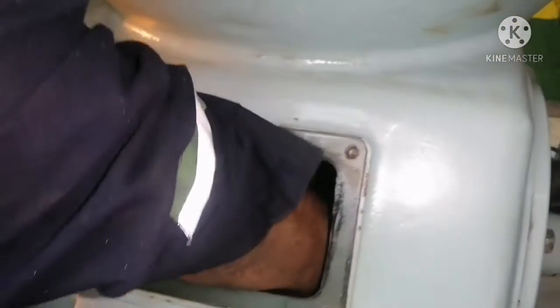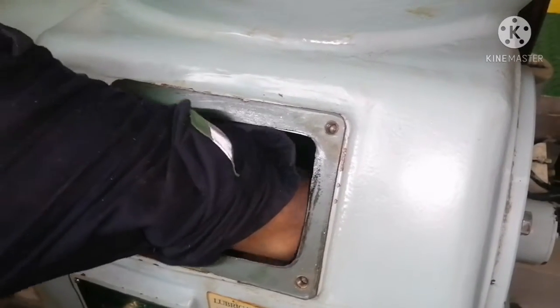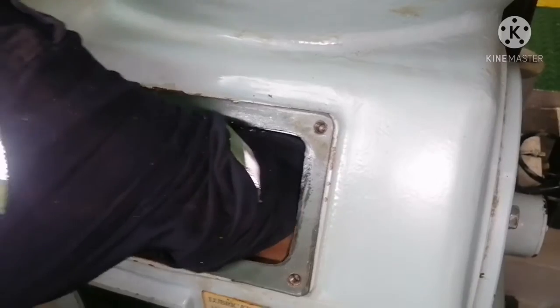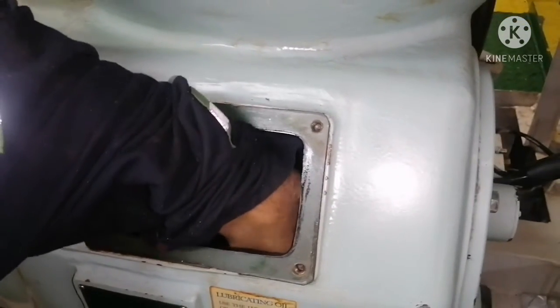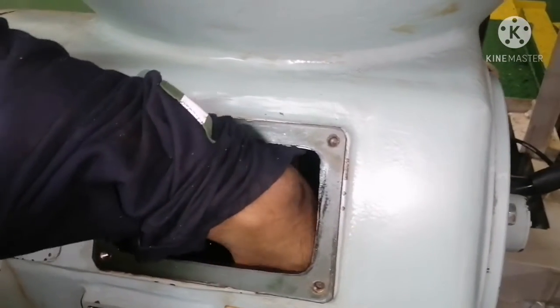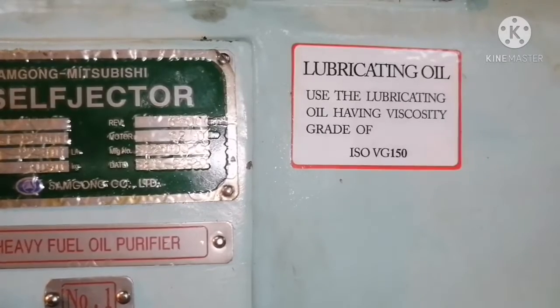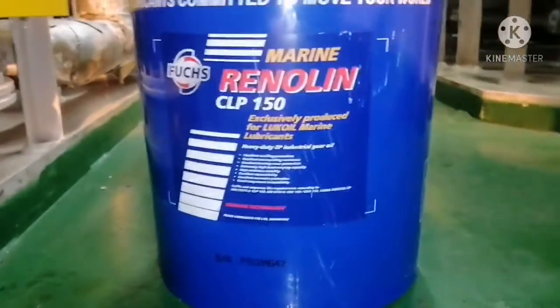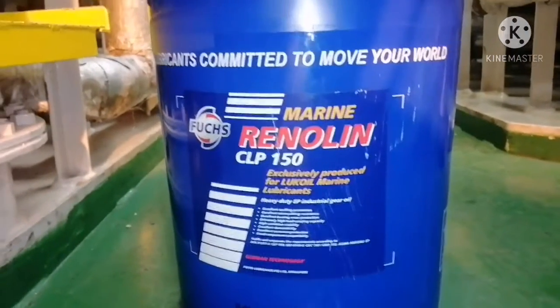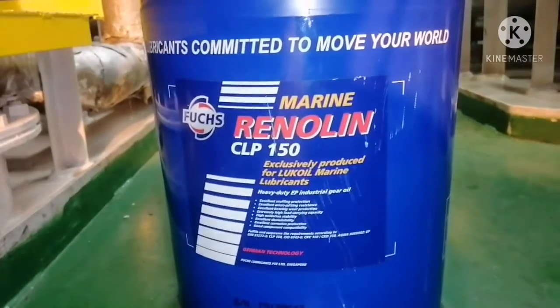Now we are doing the cleaning manually. Always use a lint-free rag when cleaning the gear oil sump so that lint doesn't get into your bearing or shaft. This is the lubricating oil we need to use. You can see the maker's recommendation: use lubricating oil with viscosity grade ISO VG 150. This is Marine Renolin CLP 150 — a gear oil recommended by the maker.